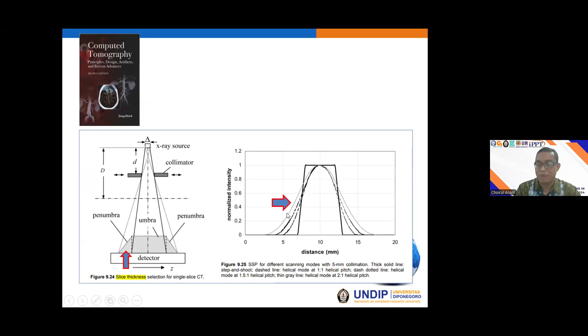This is an example of the profile of the slice thickness with different input parameters. If we use the ideal rectangle, it will be a rectangle like this. Using conventional CT, meaning the axial mode, the result looks like this. And this is when we use spiral CT. With spiral CT, if we use different pitch values, the profile is different. So this is the SSP parameter.